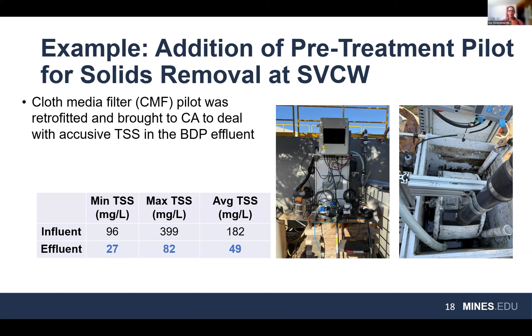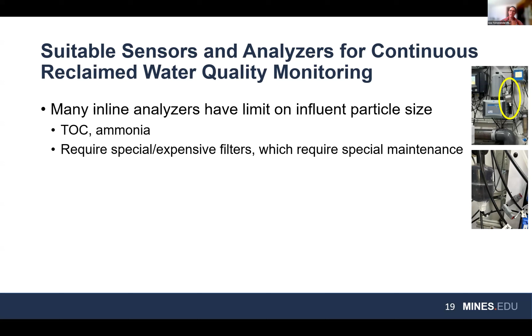Moving to the more technical side—looking at sensors and water quality monitoring on the trailer. Some of the inline analyzers we have, a biotector for TOC and an Amtax for ammonia, require special filters and special maintenance. They're circled here on the right; with smaller tubing we make sure we're not clogging those expensive analyzers. We also have an ozone sensor on the trailer to track how much ozone is actually being transferred into the water.